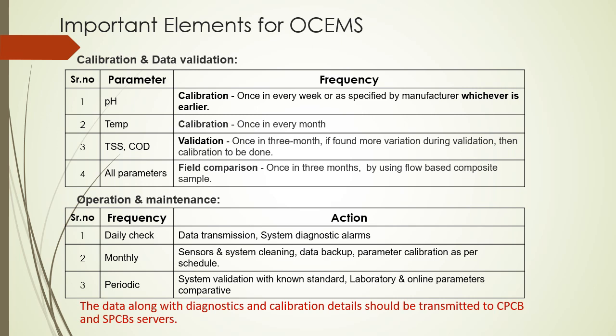and that we should not forget, because CPCB can come and inspect, and they can even ask, and it's a requirement. If you see in the red color font, the data along with diagnostic and calibration details should be transmitted to CPCB and SPCB servers. So whatever calibration has been done, we need to provide this information to CPCB and SPCB as per a scheduled frequency, right? Even in the operation and maintenance part, there are daily checks, monthly and periodic checks. All these need to be implemented at site, and it should be recorded. And whenever the CPCB and SPCB people ask us, we need to provide them these details.